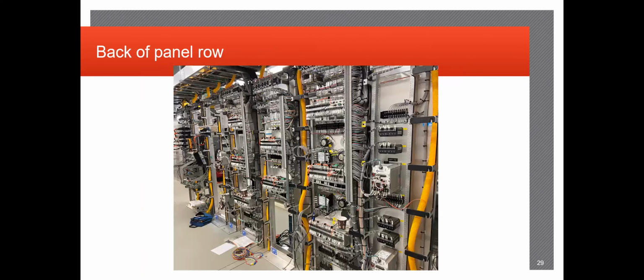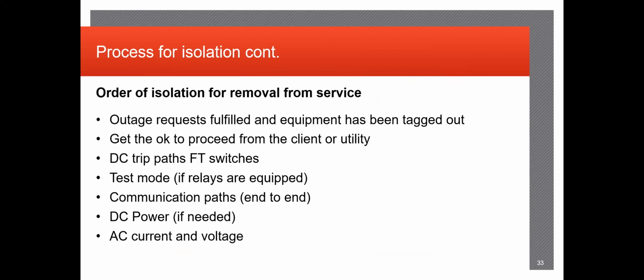And then let's see how this goes, because there's a lot of odds and ends that you may see from time to time. So I just like to see what he has laid out. So your DC trip path, yep, good. Communication path. Test modes, again, you won't really see this unless you're working with GE specifically. They're usually the only ones that I've seen that have been equipped with it. I'm sure there are other brands, but most of the time it'll be SEL, and I haven't really seen a client either that uses the test mode for anything.